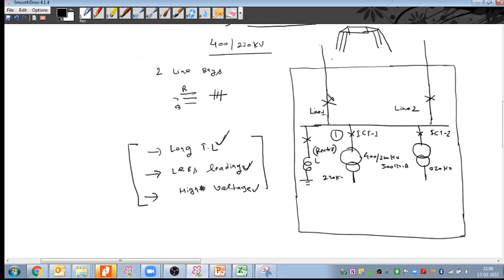So whenever there is a longer transmission line with less loading, and the third condition, whenever there is any high voltage system. If the voltage is less, then it will not become very effective. But whenever there is a high voltage system, a long transmission line, high ground height, and less loading, in that case the shunt capacitance between the conductor and the ground will inject reactive power into the system. Due to the injection of reactive power by the shunt capacitance, when loading is less and reactive power injected by the capacitance is higher, the voltage will increase.